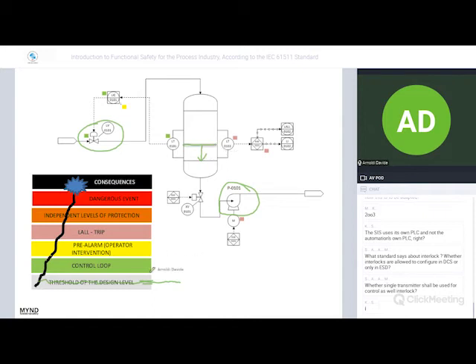the level decreases. So our scenario meets the failure of the control loop and meets the pre-alarm that is here. This is normally what is inside a control room. The operator can see that something is going toward a dangerous situation. And if the operator has time, maybe they can resolve the situation. If not, we reach what is called the hazardous situation, which probably means this level of water, low level.